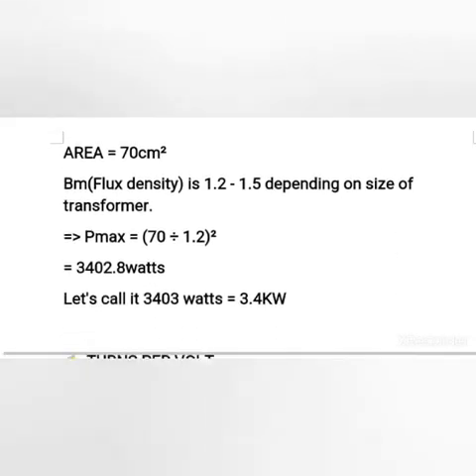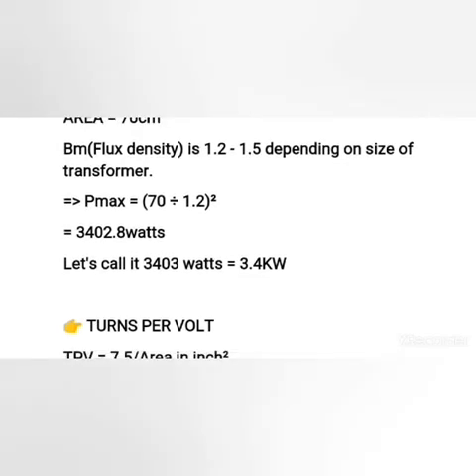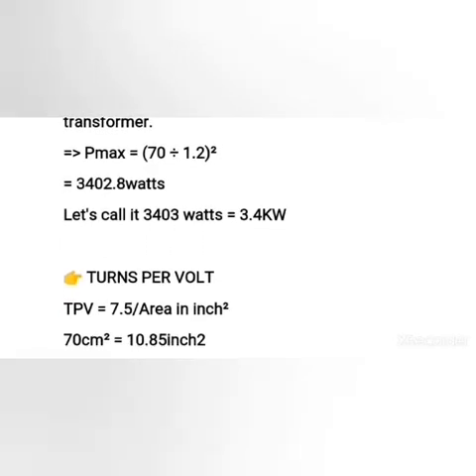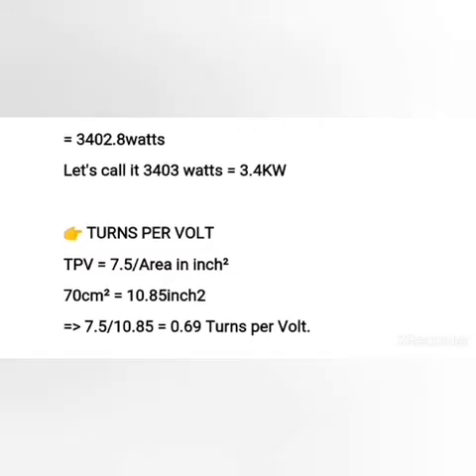The next thing is to find our turns per volt. The formula is 7.5 over area in inches squared. We know our area in centimeters squared is 70, so we convert from centimeter squared to inch squared, which gives us 10.85 inch squared. So 7.5 over 10.85 gives us 0.69 turns per volt. Some people ask how we got 7.5 — it's actually a constant, and for convenience it's always better to substitute with that value.